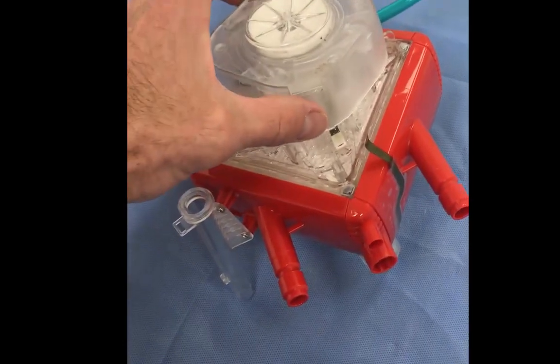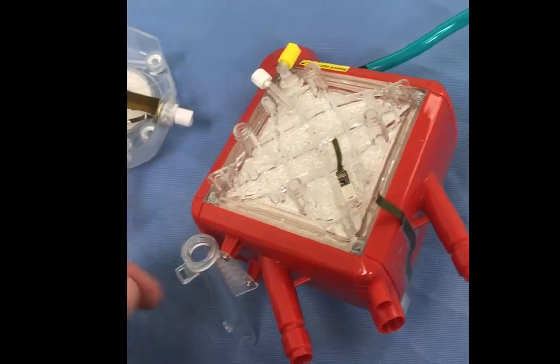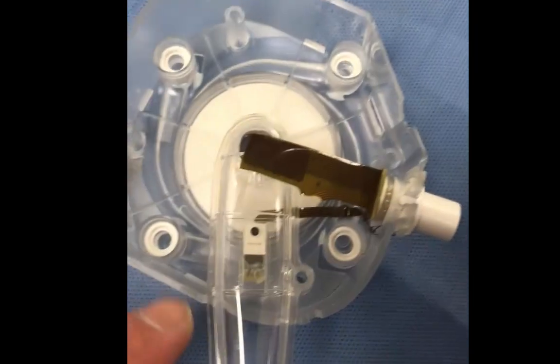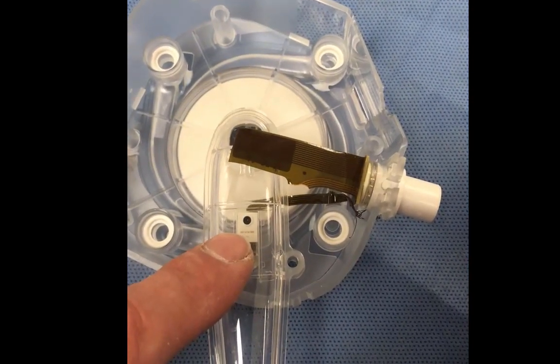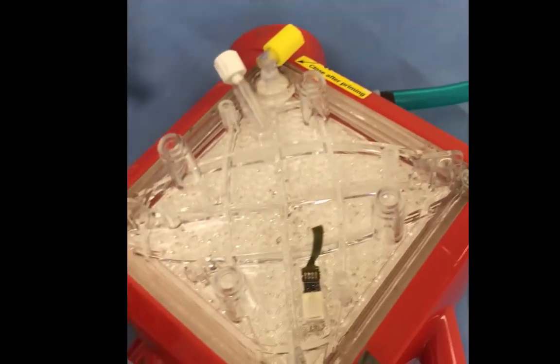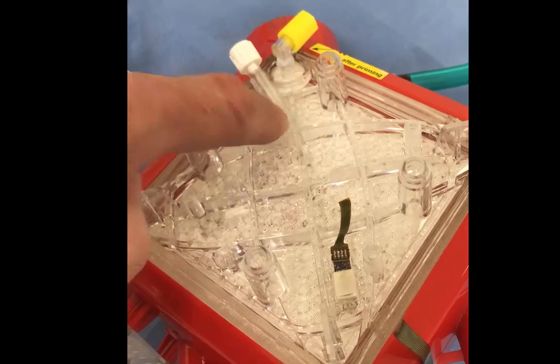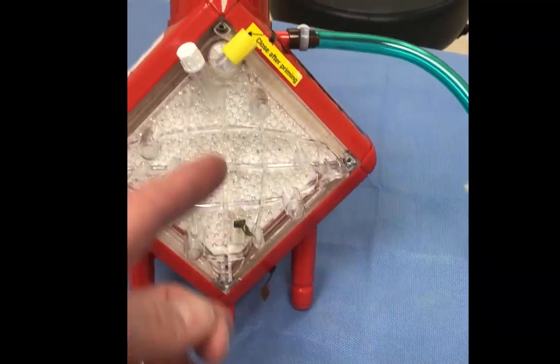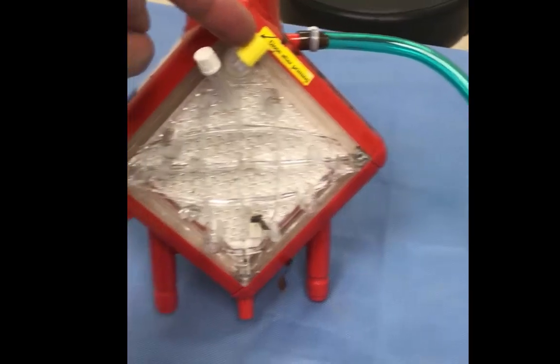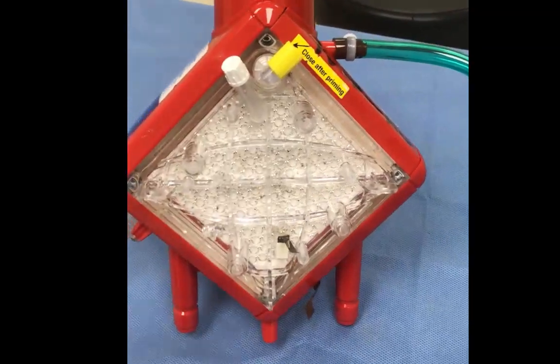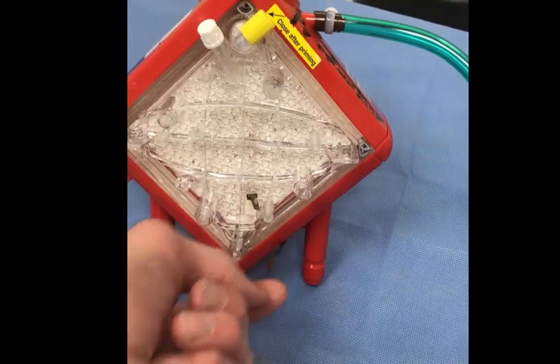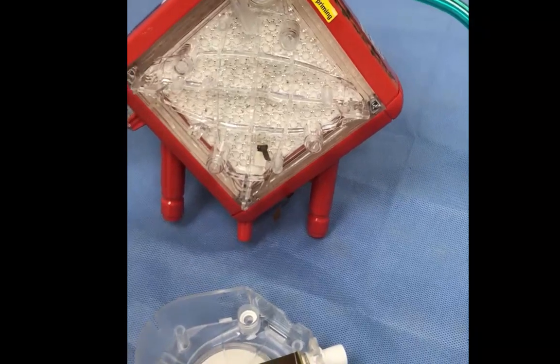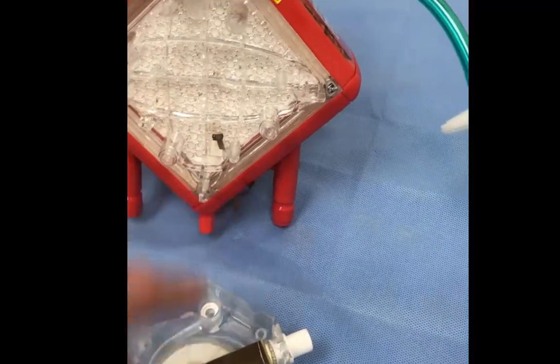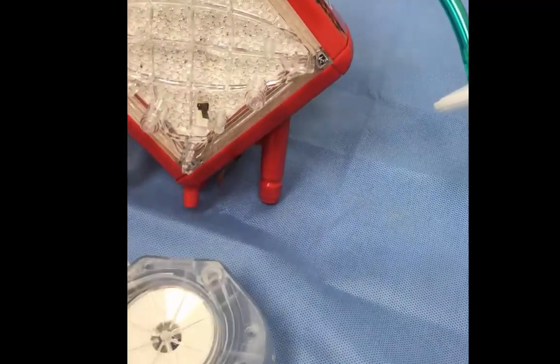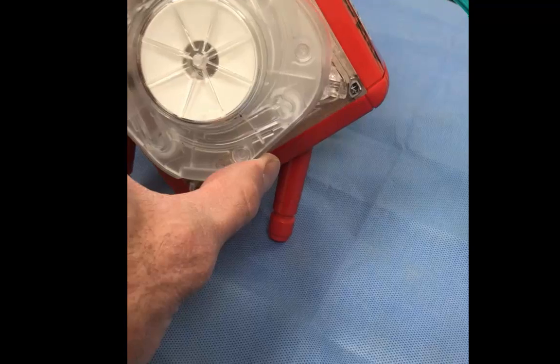So when you disconnect the pump from the back of the oxygenator, you fold it out, you can see a pressure sensor there, and a pressure sensor inside the inlet of the centrifugal pump. The pre-membrane sample port has been moved to the top of the oxygenator here. Oxygenator sits like this. There's your sample port. Here's the air venting port. Sample port, air venting port. And the data from the post-membrane, pre-membrane, and venous line pressure, pressure, temperature, pressure, all comes out this cable to the surface here.